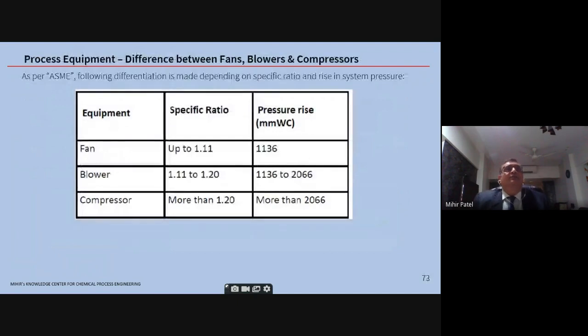Okay. So now the difference between fans, blowers, and compressors. As per ASME, the following differentiation is made depending on the specific ratio, the pressure ratio basically, and rise in system pressure. So for a fan, you can go up to 1.11. So atmosphere is 1, you can go up to 1.11. The pressure rise in mm water column is shown here. Okay. And the blower is 1.11 to 1.2. And the compressor is basically more than 1.2. So this is the basic differentiation between the 3 types.